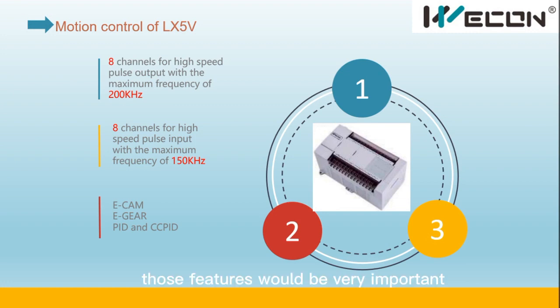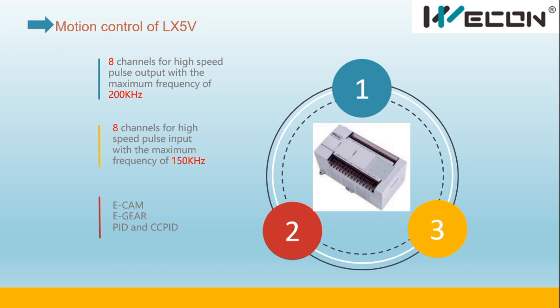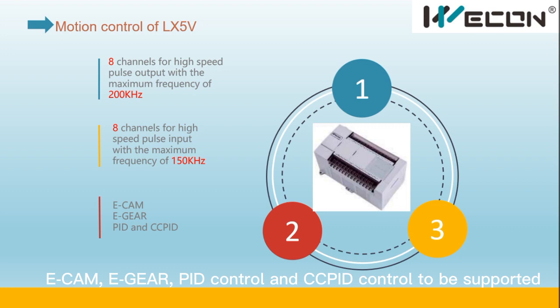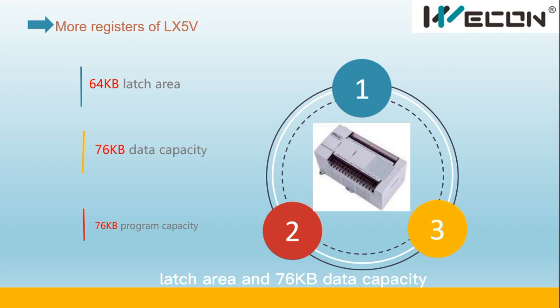For motion control, the LX5V PLC's features are very important. High-speed pulse output can be eight channels at 200kHz, high-speed pulse input can be eight channels at 150kHz, and E-cam and E-gear are supported, as well as cascade PID control. The LX5V also supports more registers — a 64K latch area and 76K data and program capacity.